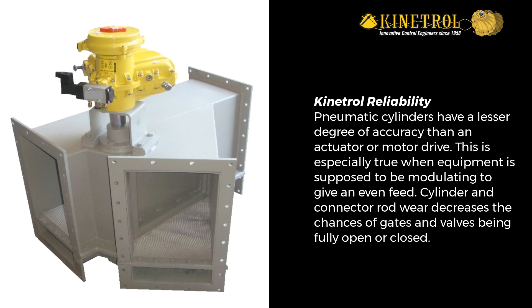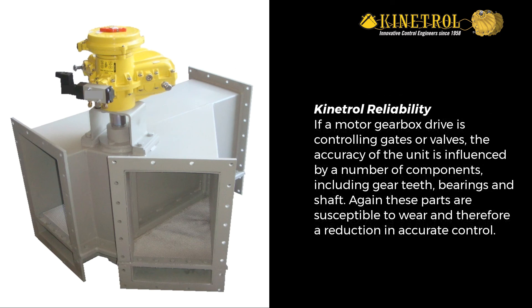Cylinder and connector rod wear decreases the chances of gates and valves being fully open or closed. If a motor gearbox drive is controlling gates or valves, the accuracy of the unit is influenced by a number of components including gear teeth, bearings, and shaft. These parts are susceptible to wear and therefore a reduction in accurate control.